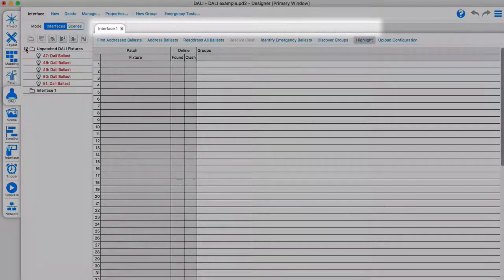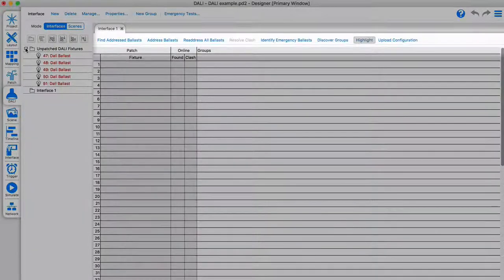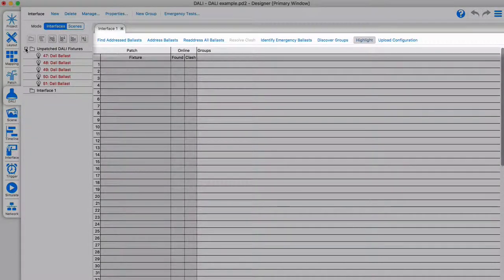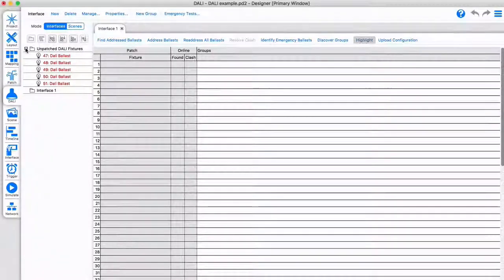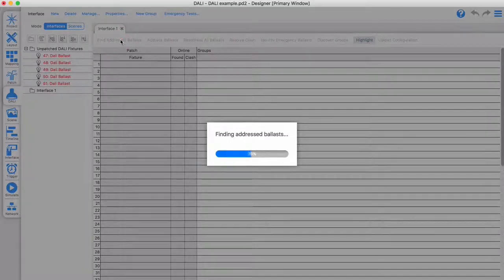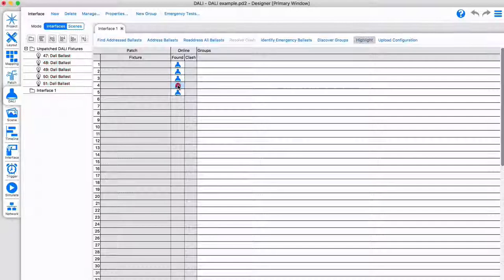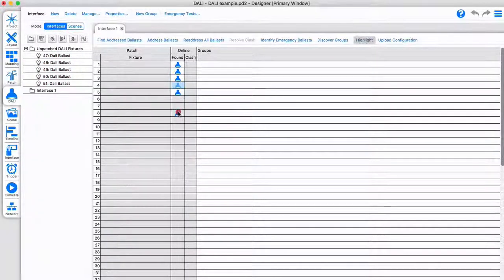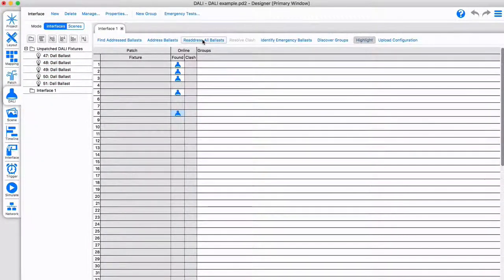If your hardware is connected and you have uploaded the project once, you will find commissioning tools for the DALI bus here. You can discover or address ballasts in a new installation. When required, you can re-address the ballasts via a simple drag and drop or re-address all automatically.